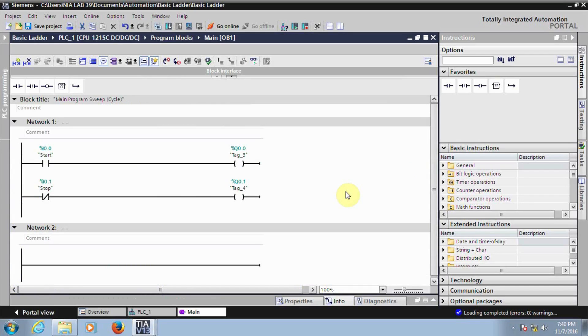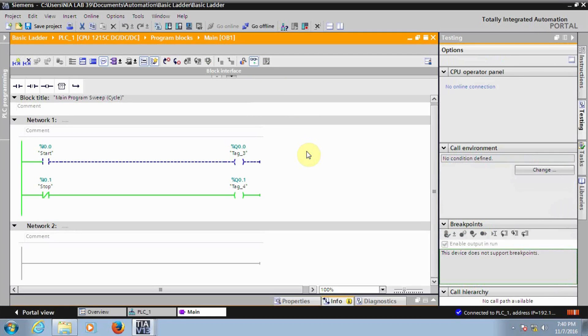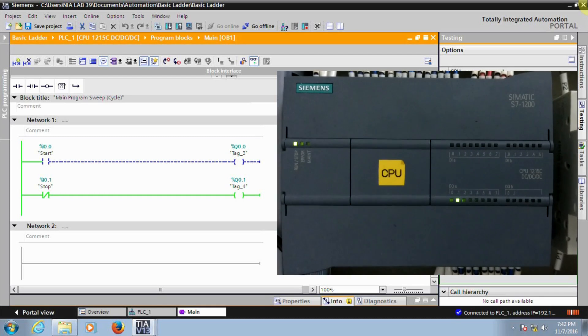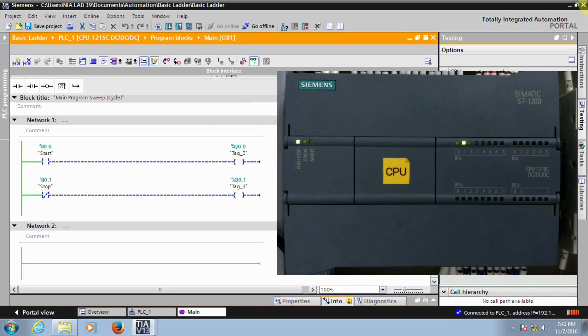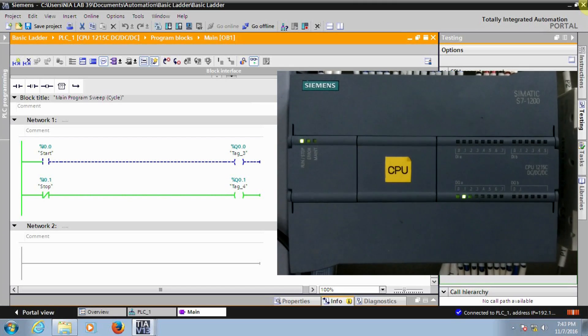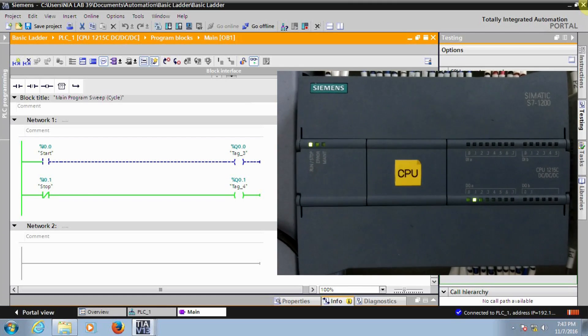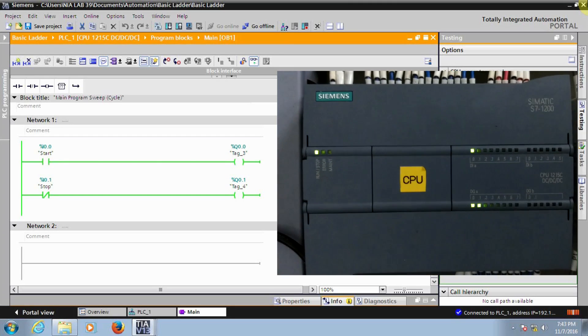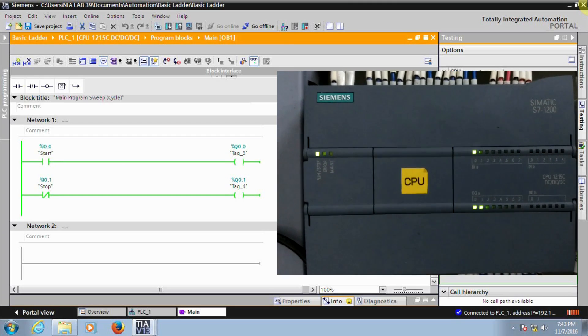If you want to see the operation on the screen, click on the Monitor option. Now you can see in the program: one is a Normally Open contact and the other is a Normally Closed contact. You can see the output status in the PLC — it is going high. If I give an input to the particular terminal, the output goes off, and if I remove the input it will turn back on. Similarly for the Normally Open instruction: when I give the input, the output will also turn on.